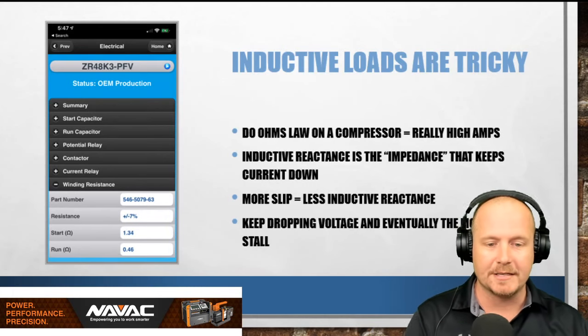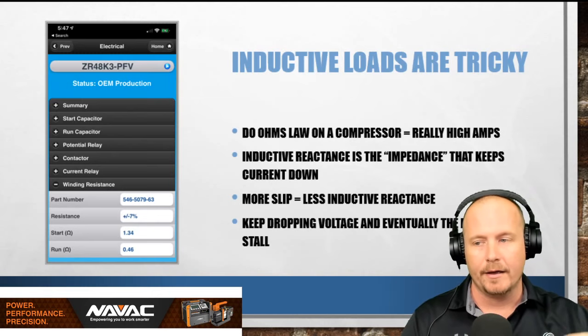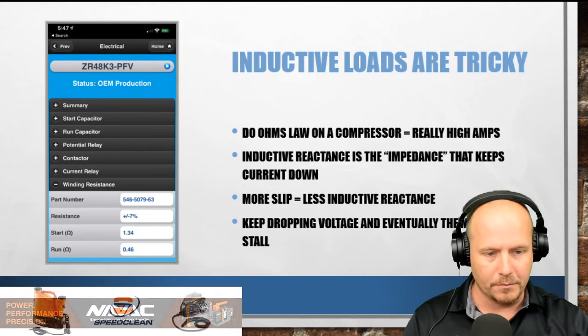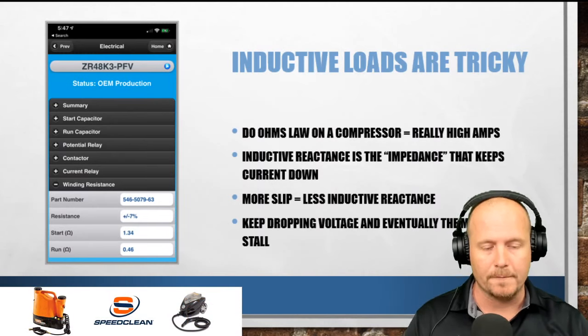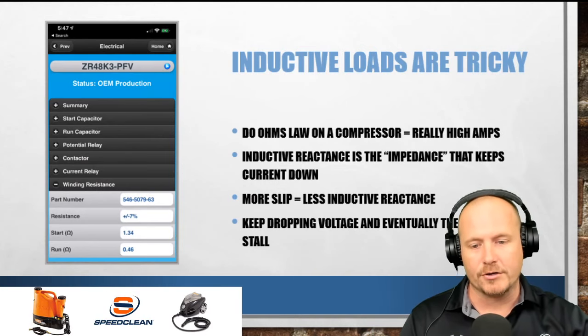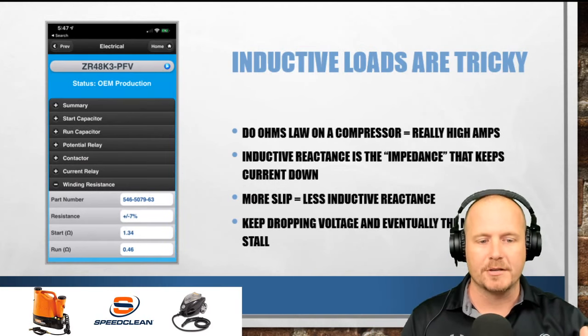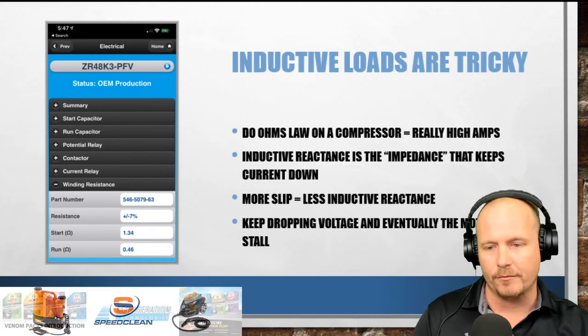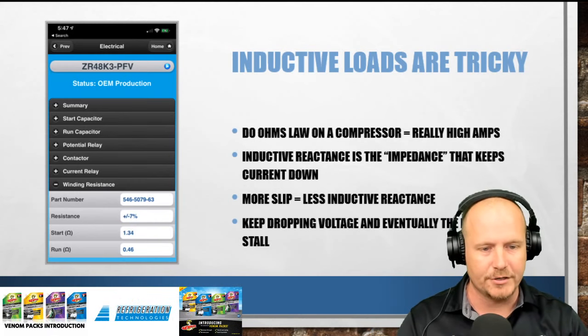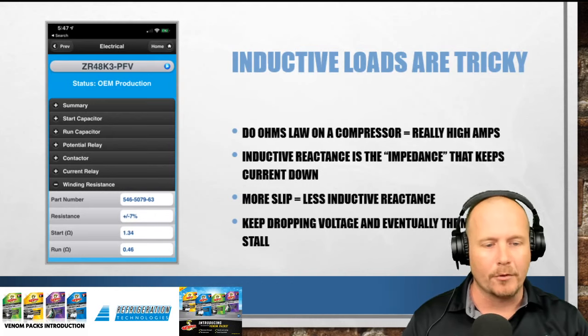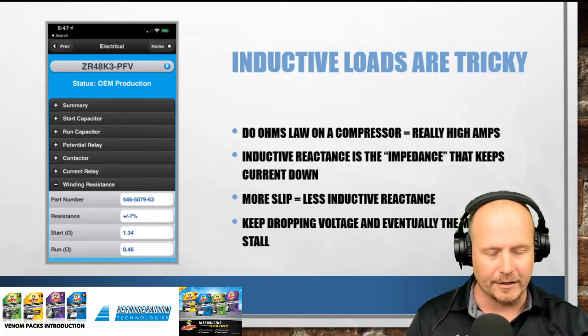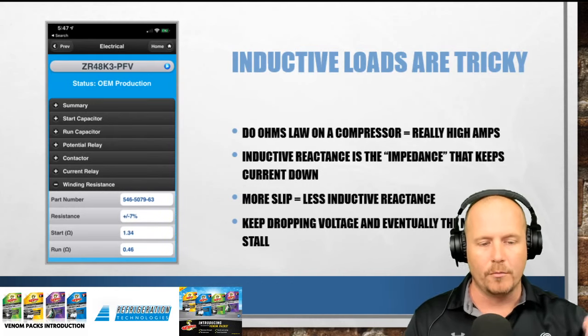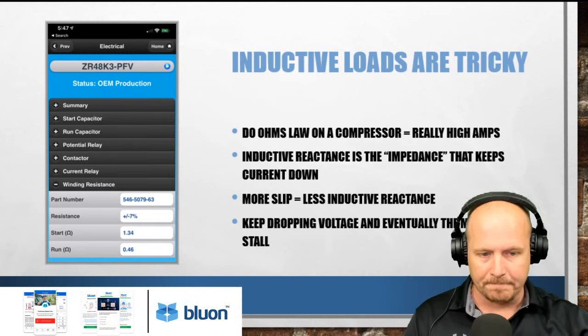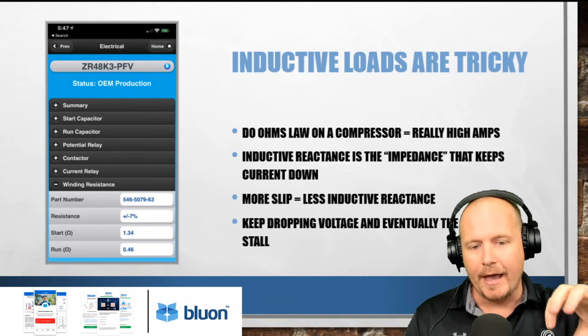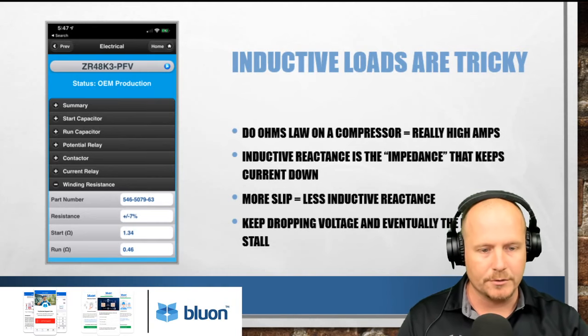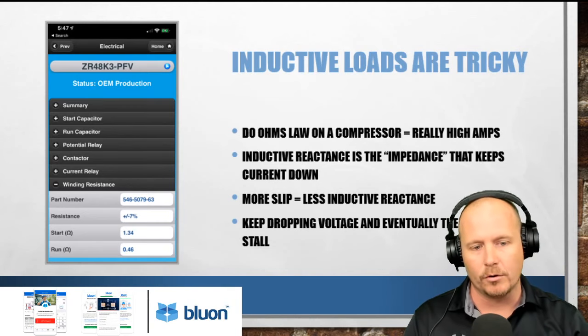So what really happens inside of a motor when you apply inappropriate voltage, when you apply voltage that's too low to the motor, then that motor starts to run hotter. It may not actually run hotter than it was before, but there will be more percentage of waste towards heat. So from a very practical standpoint, the motor will run inefficiently. If you apply too low a voltage, the motor will run inefficiently. Okay, so that's one critical thing. And eventually the motor will stall. So eventually if you drop the voltage low enough, the motor will stall.